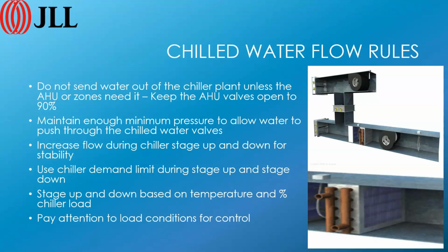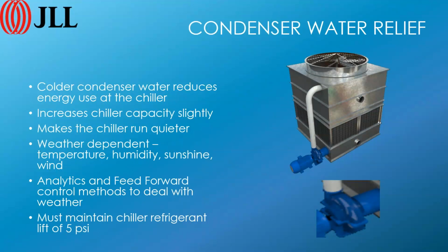This allows you to stage up and stage down a little bit better. You may want to temporarily increase flow when you're doing stage up and stage down operations, and control chiller demand. Then once the new staging condition has been reached, after a few minutes you just release it slowly and let it go back to equilibrium. We generally like to stage up and down based on temperature and percent chiller load for that reason. We don't really stage up and down on tons anymore, for another reason that you're going to see shortly. It doesn't make any sense to stage up and down on tons.